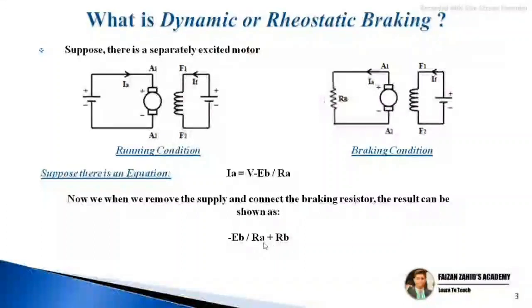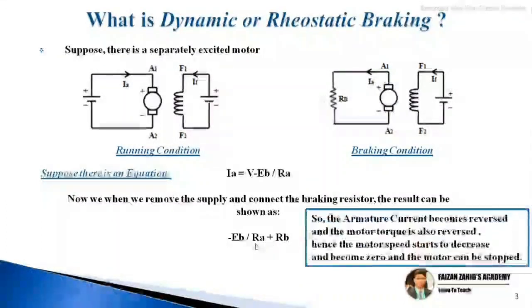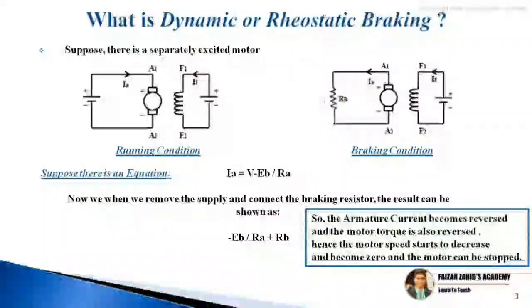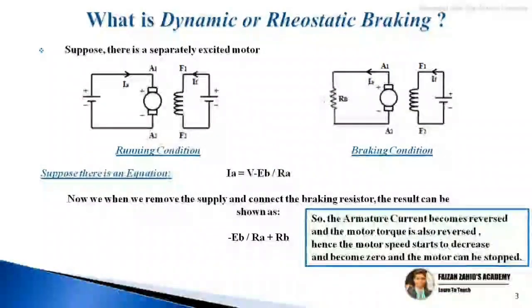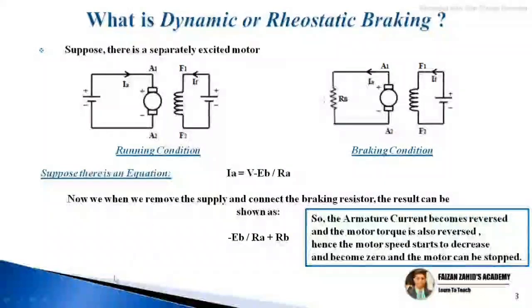This means the armature current becomes reversed and the motor torque is also reversed. Hence the motor speed starts to decrease and becomes zero, and the motor can be stopped. This is how the dynamic or rheostatic braking system operates.